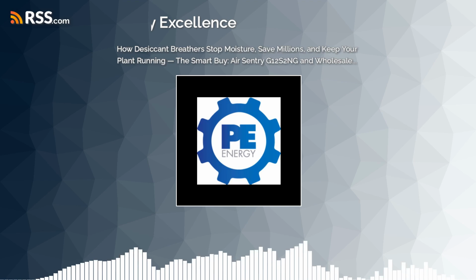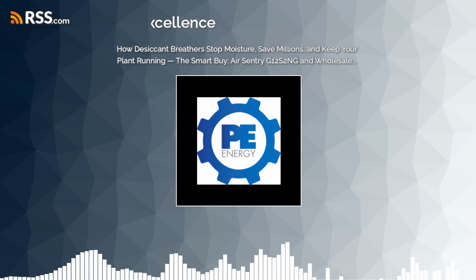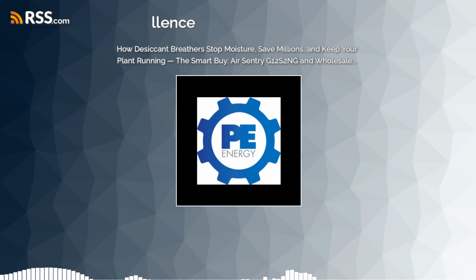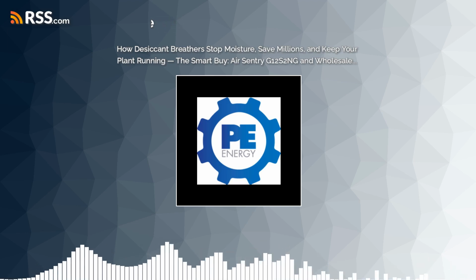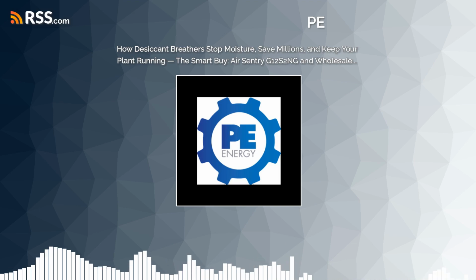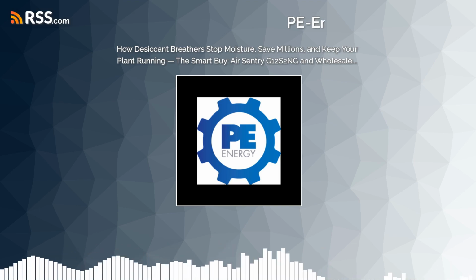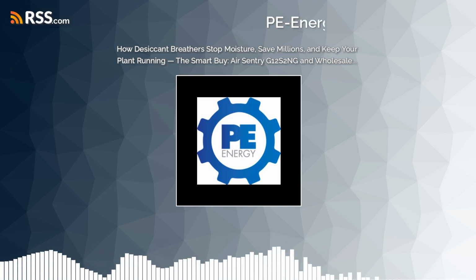On paper, you're right. The bulk silica gel, especially that blue indicating gel mentioned in the text, is much cheaper per pound. For a massive transformer that holds, say, 50 pounds of desiccant, you absolutely want to refill. You're not going to swap a giant steel housing every month.